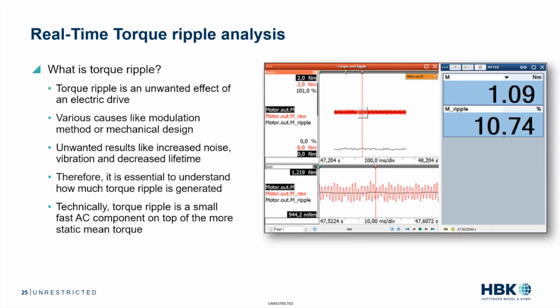So let me touch on that torque ripple, which is really a mechanical noise. It's an unwanted effect of an electric drive. Various causes like modulation, the method of modulation, or the mechanical design will cause torque ripple. And naturally, it's unwanted. It's going to add increased noise, vibration, and it will even possibly decrease the lifetime of the system. So it's essential to understand how much torque ripple is generated. And the HBK Power Analyzer solution does offer the ability to easily measure torque ripple. It automatically sets up the appropriate analysis equations to do so.